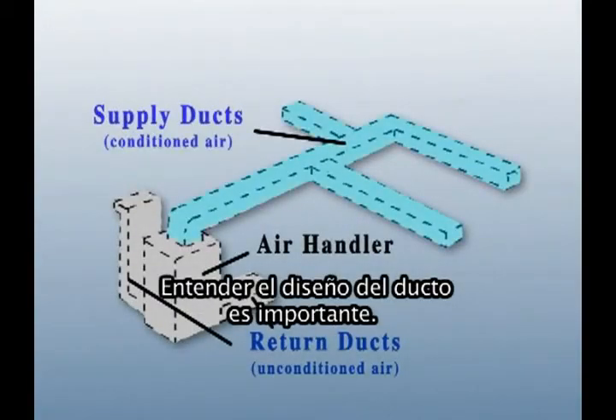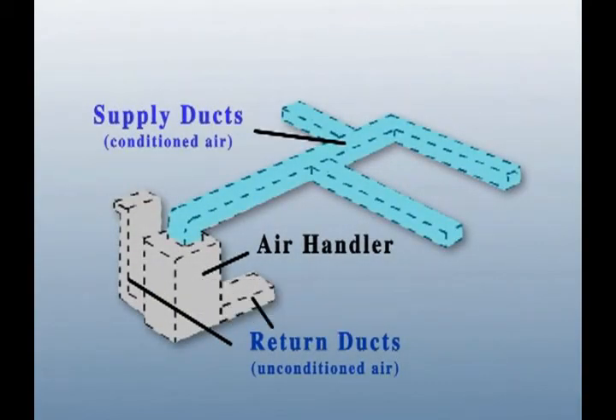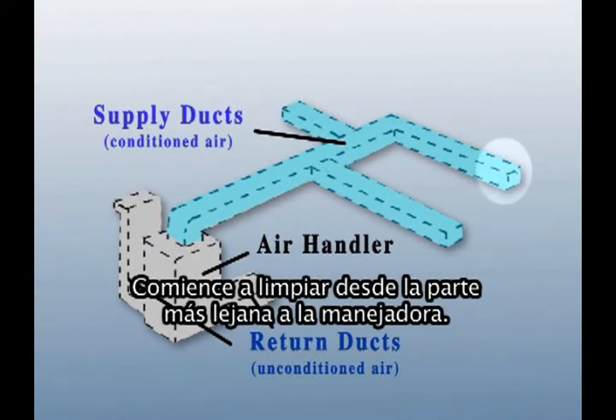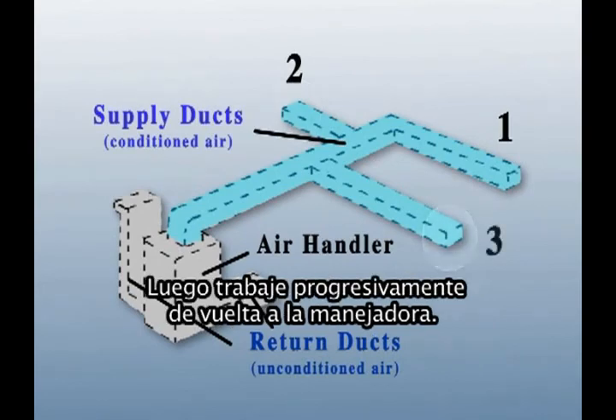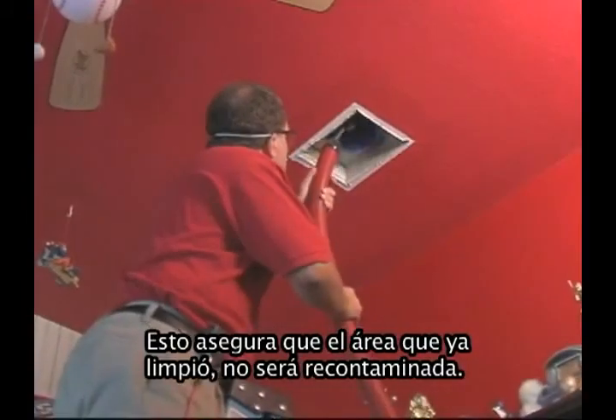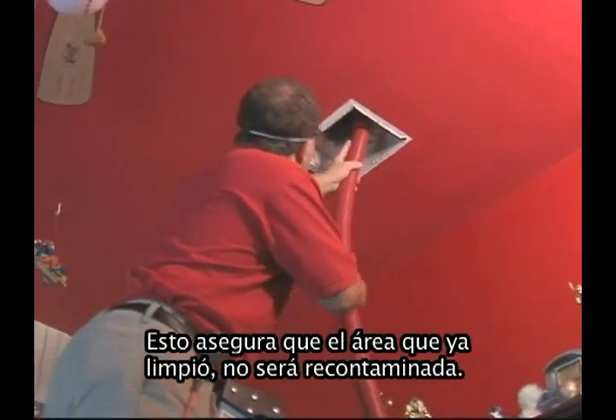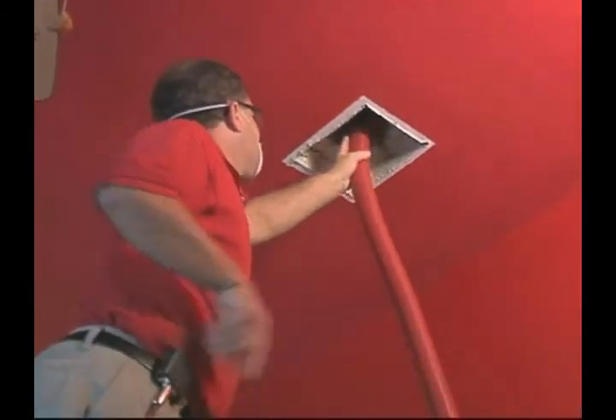Understanding the layout of the ductwork is important. You will start cleaning the supply side of the air ducts, beginning with the ducts farthest from the air handler. Then clean the other supply air ducts, working progressively back towards the air handler. This ensures that the areas you have already cleaned will not be recontaminated.